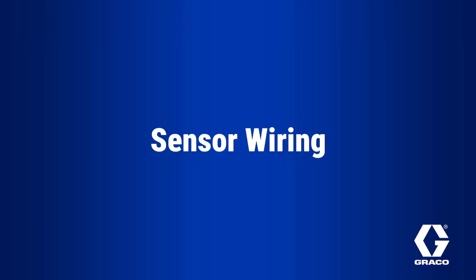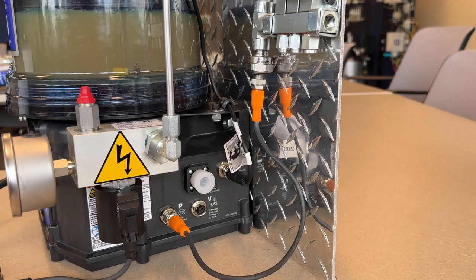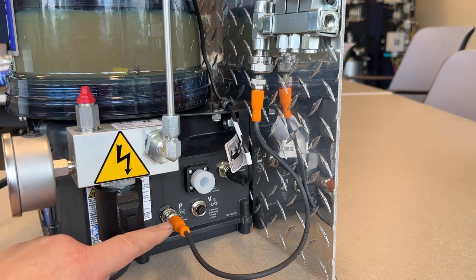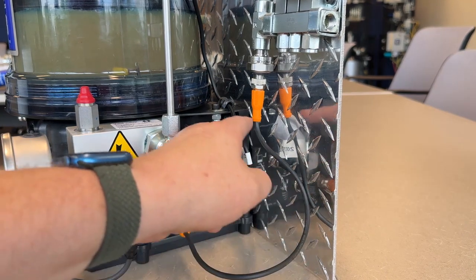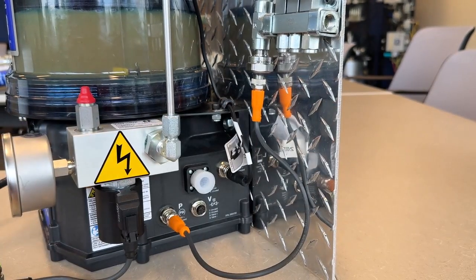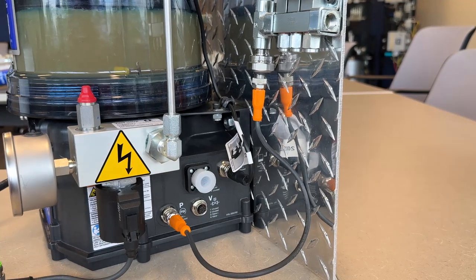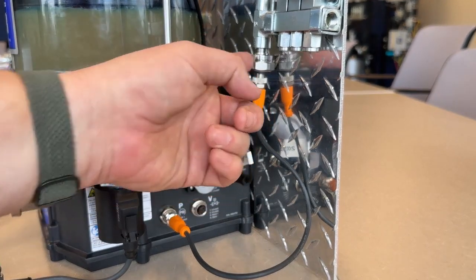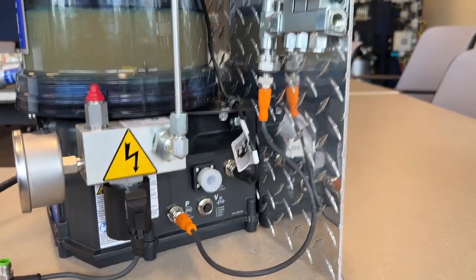If temperature changes are not the culprit and there are no breaks or blockages in the system, the next step in troubleshooting this alarm is to trace the cable from the P input to the pressure sensor. Make sure it is connected at both ends and that the cable has not been cut or damaged. Sometimes the sensor is mounted next to the pump, but often it is mounted some distance away.